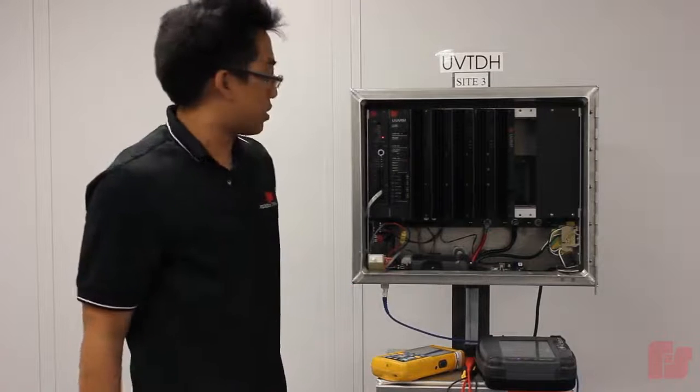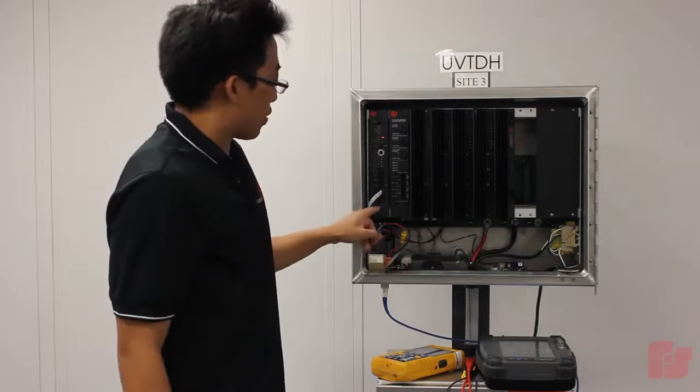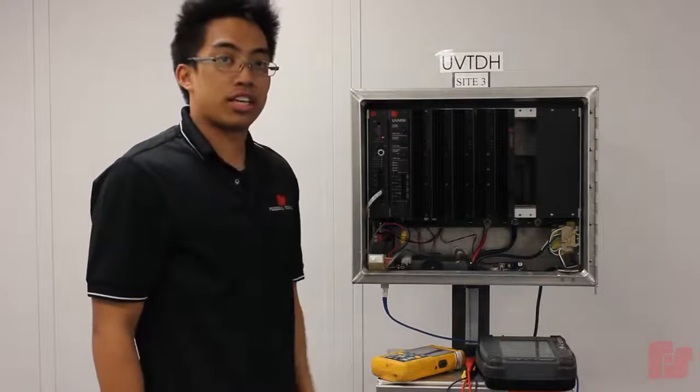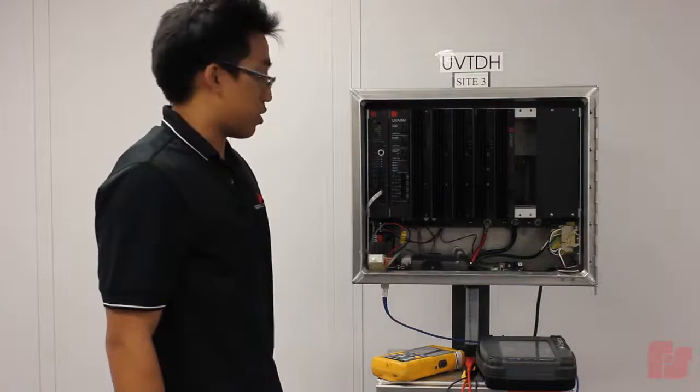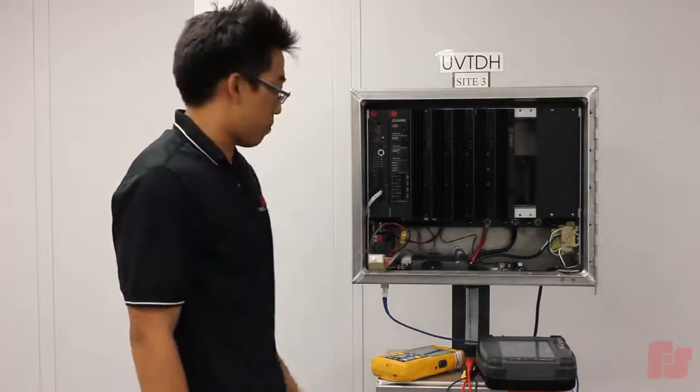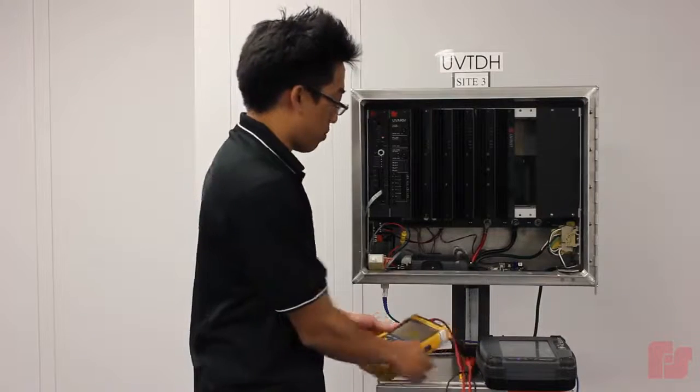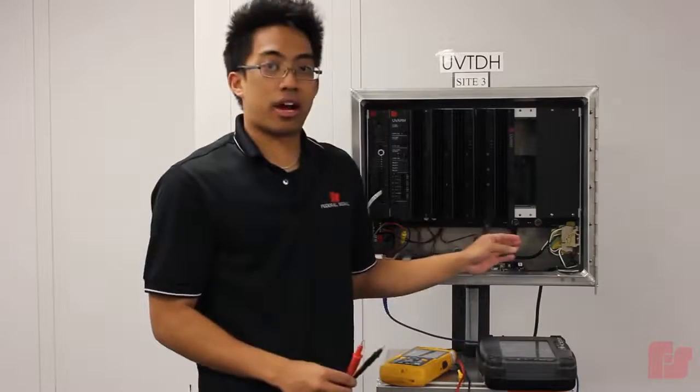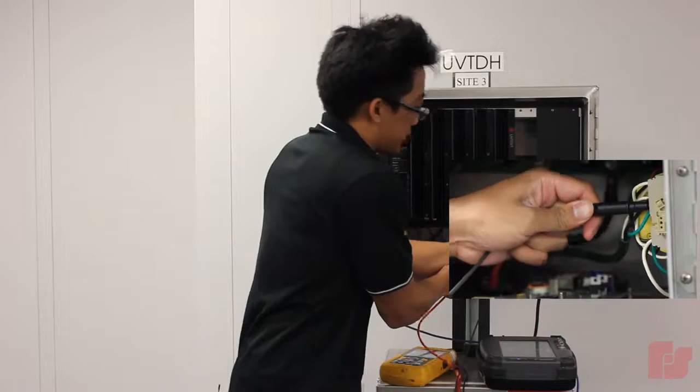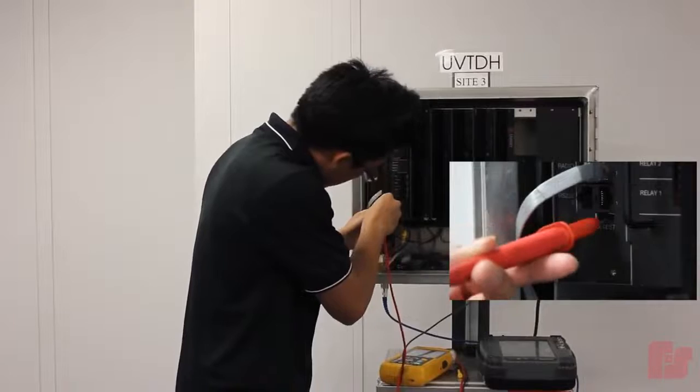And later on the next step is going to be observing the tone coming through the RX test pin and checking that it's at a 1 volt peak to peak level. And to do that we're going to use the scope. So I'm going to go ahead and connect my scope and I'm going to use the cabinet's terminal block to ground it.